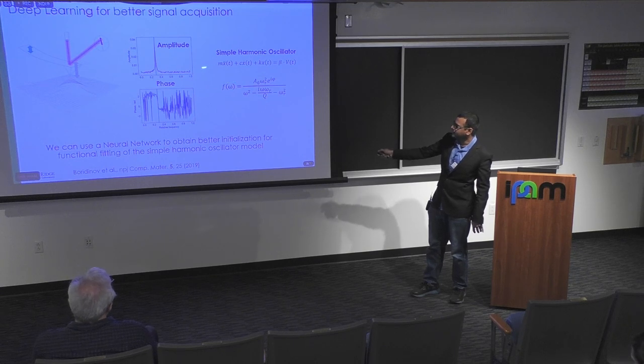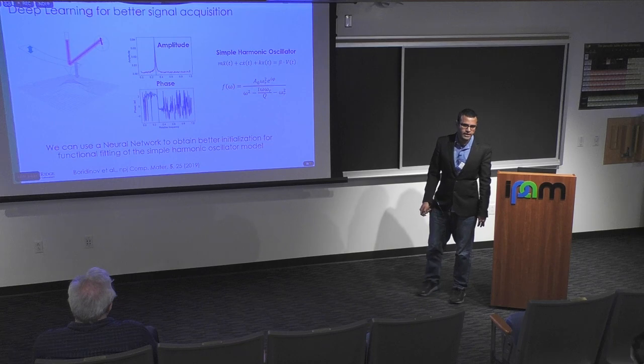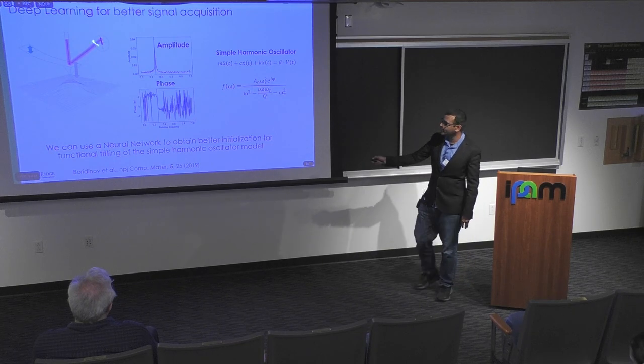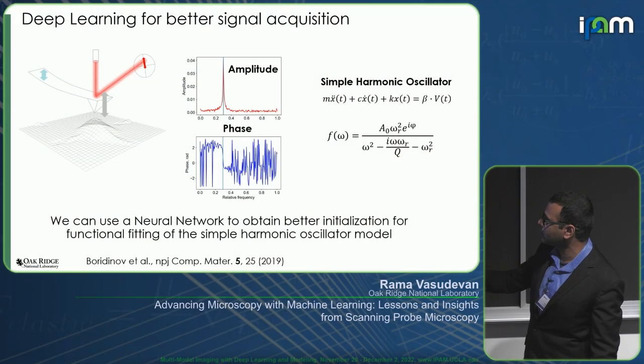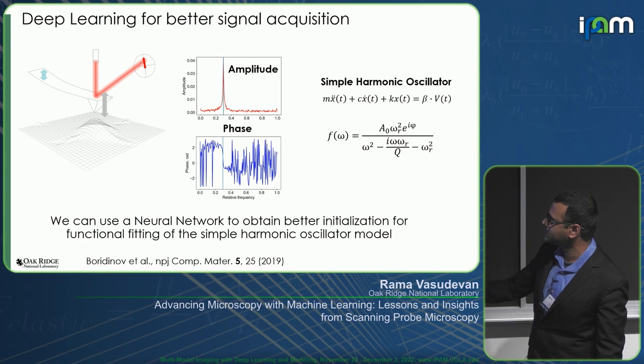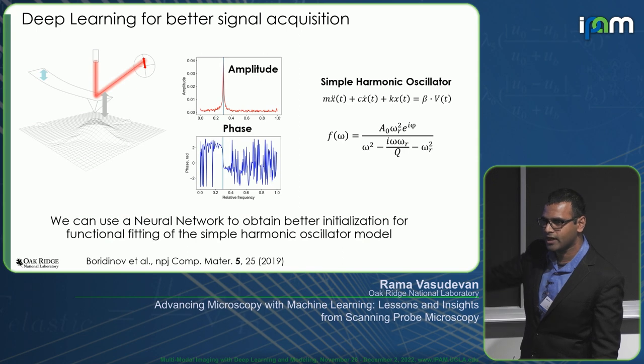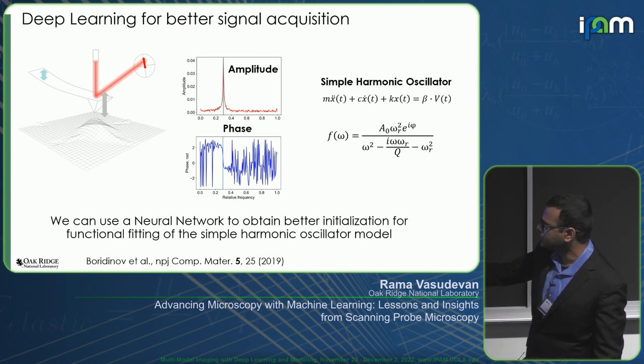We take our data from the AFM and find the fitting parameters for the simple harmonic oscillator model. Typically we get this data, fit it to this particular model, and extract parameters such as the amplitude of oscillation, the phase of oscillation, the resonant frequency—where this amplitude is maximum—and the quality factor of the cantilever, which is the full width half maximum of this particular peak.